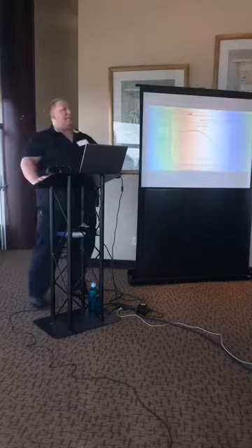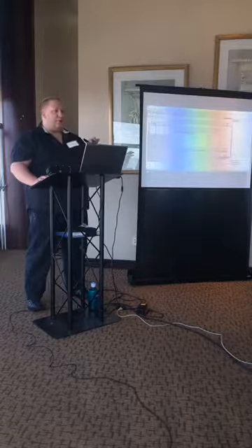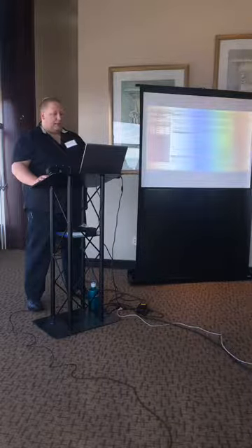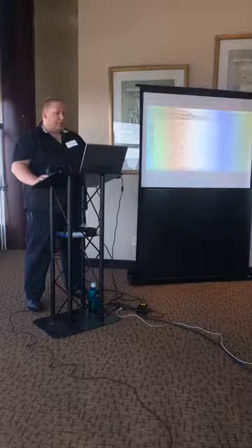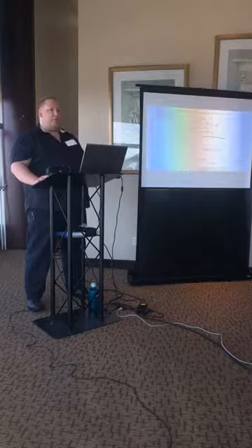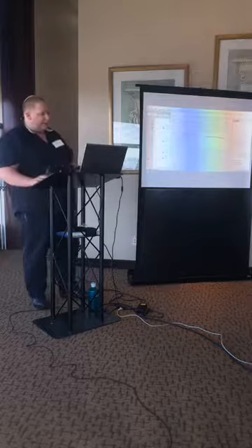And I want to apply that pump curve to my very bottom pump in that system. And so what I'm going to do is click on apply pump data. And I'm going to physically change that pump junction. So I click on the pump I want to change right here. I'm going to apply it. So now when I go back into my workspace here, this pump is now using that pump curve. And you can see that it's based upon an RPM of 2,632 RPM, and it is a 10.4-inch impeller trim.